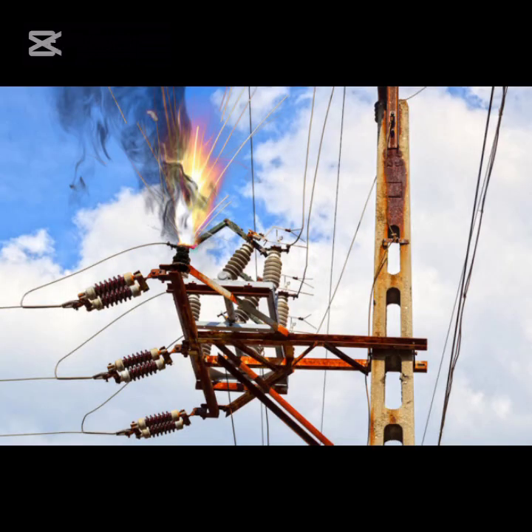Short circuit results in an abnormally high current, known as short circuit current, flowing through the circuit. During a short circuit, the voltage at the point of fault drops to nearly zero, creating a low resistance path for current flow. This can cause severe damage if it is not interrupted quickly.